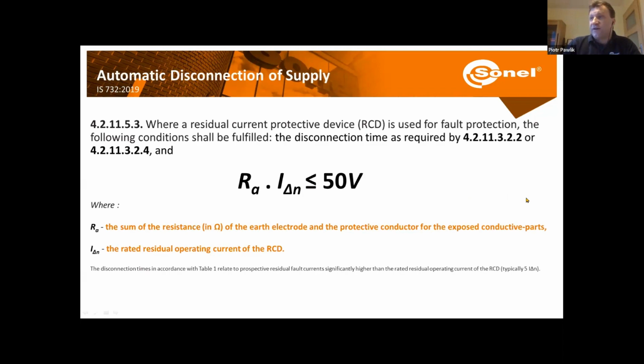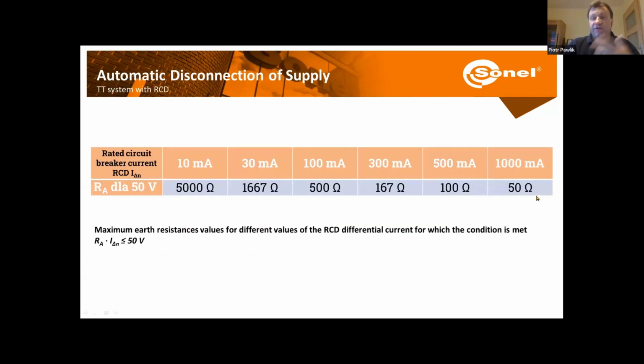So that's how we calculate the disconnection in case of a TT network secured with RCDs. And here we have some examples. So depending on the rated current of the RCD, these are the maximum values of the resistance of earth electrode and the resistance of the PE wires in the walls that we can get. So for example, when we have the RCD with 30 milliamps current, then the maximum value of resistance of earth electrode and the wires in the wall, that will be 1667 ohms.